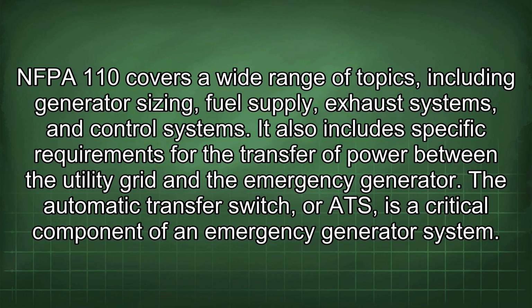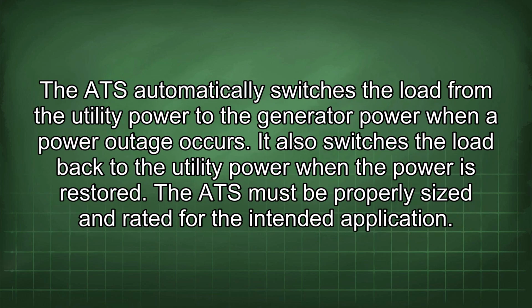NFPA 110 covers a wide range of topics, including generator sizing, fuel supply, exhaust systems, and control systems. It also includes specific requirements for the transfer of power between the utility grid and the emergency generator. The automatic transfer switch, or ATS, is a critical component of an emergency generator system. The ATS automatically switches the load from the utility power to the generator power when a power outage occurs. It also switches the load back to the utility power when the power is restored.